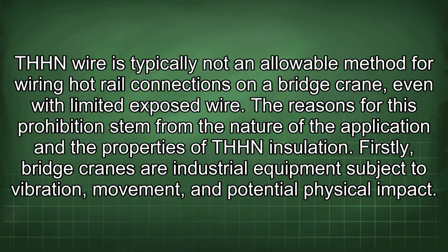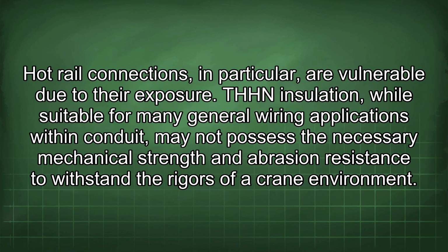THHN wire is typically not an allowable method for wiring hot rail connections on a bridge crane, even with limited exposed wire. The reasons for this prohibition stem from the nature of the application and the properties of THHN insulation. Firstly, bridge cranes are industrial equipment subject to vibration, movement, and potential physical impact. Hot rail connections, in particular, are vulnerable due to their exposure.